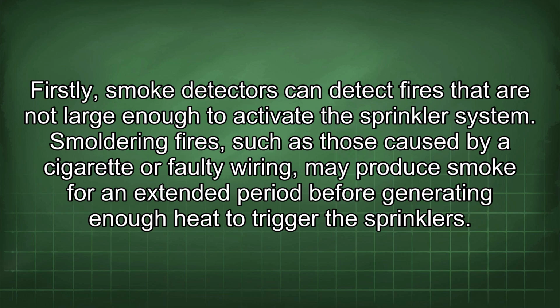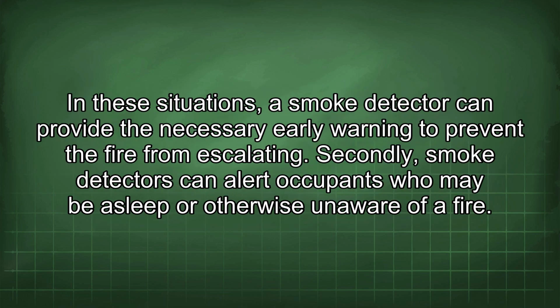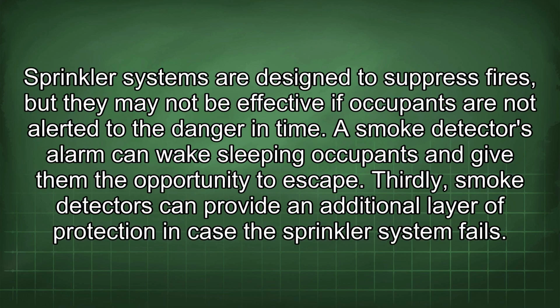Smoldering fires, such as those caused by a cigarette or faulty wiring, may produce smoke for an extended period before generating enough heat to trigger the sprinklers. In these situations, a smoke detector can provide the necessary early warning to prevent the fire from escalating. Secondly, smoke detectors can alert occupants who may be asleep or otherwise unaware of a fire. Sprinkler systems are designed to suppress fires, but they may not be effective if occupants are not alerted to the danger in time. A smoke detector's alarm can wake sleeping occupants and give them the opportunity to escape.